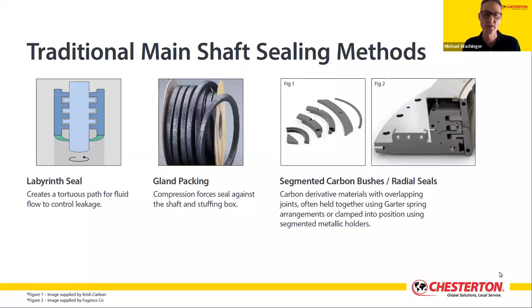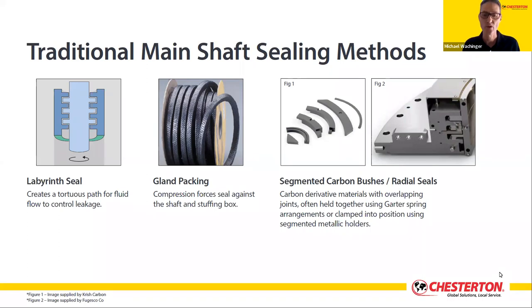Packing works by compressing material to seal against the stuffing box bore and the turbine shaft radially. The more you compress the packing, the harder it seals against those two elements, and so the lower the leakage rate — however, the higher the wear rate on the shaft sleeve becomes. Early packing designs required significant water to keep it cool from the friction generated by the turning shaft. Using supply water as cooling lubricant meant abrasive materials from the river became embedded in the packing and accelerated wear of the main shaft sleeve. Leakage would sometimes overwhelm the station's drainage system, leading to contamination of oil-lubricated bearings and overall flooding of the station.